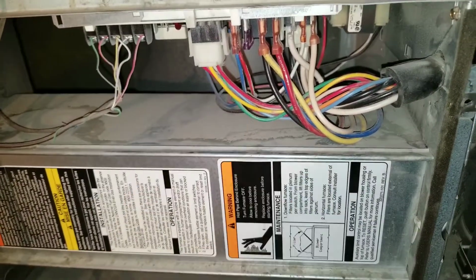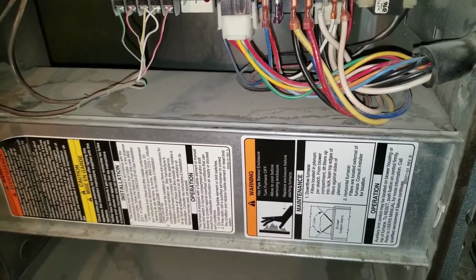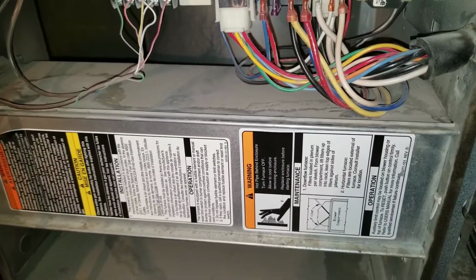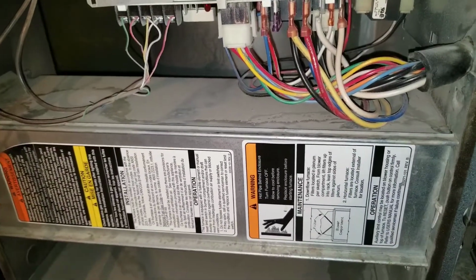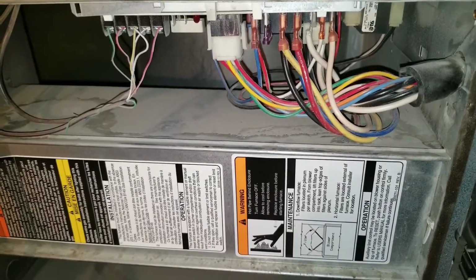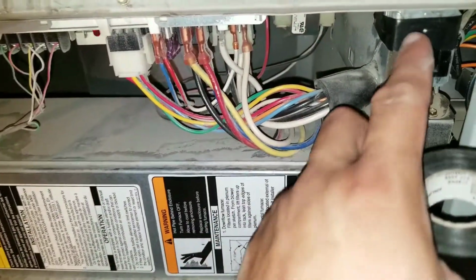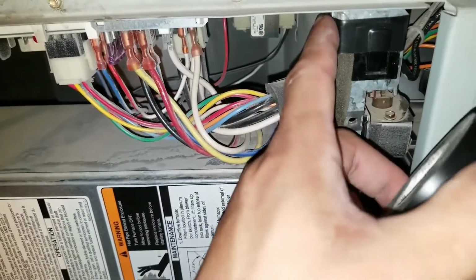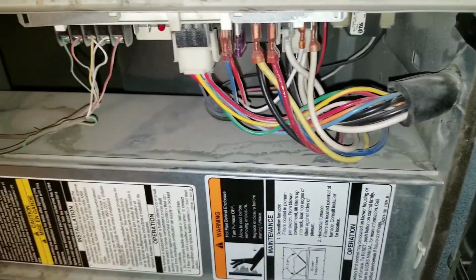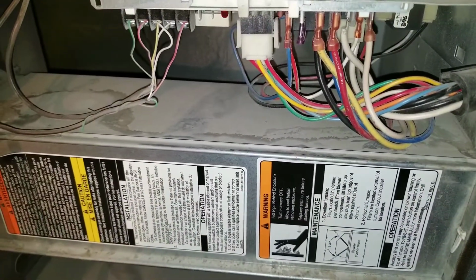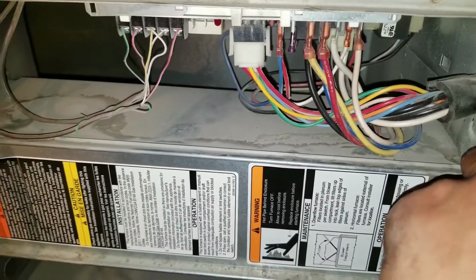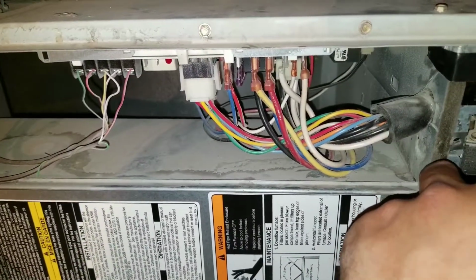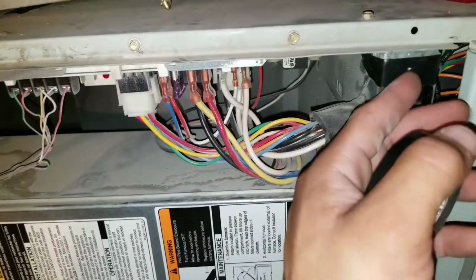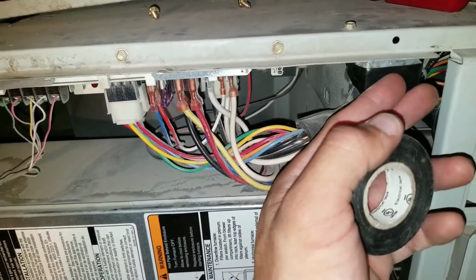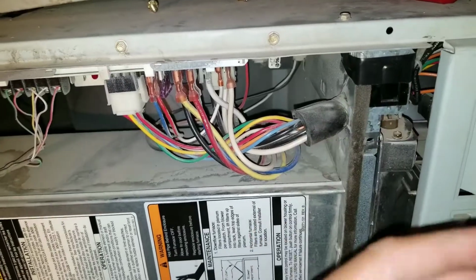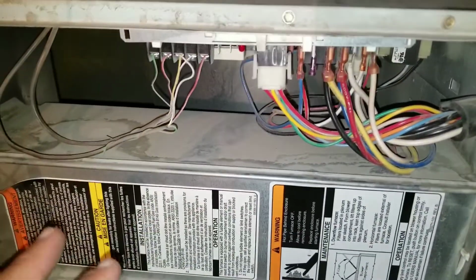Just be careful when you're working on this board. There is going to be power, both 120 volt and low voltage wiring. So just be very careful when you're working on your system. So here I just took some electrical tape and I wrapped it around my safety switch. And this is going to allow me to just come over here and work on this board. Just be careful, as I said, because right now I'm tricking the system into thinking that this panel is on. When you remove this panel, this safety switch will actually disengage, and it will kill the power to your board.